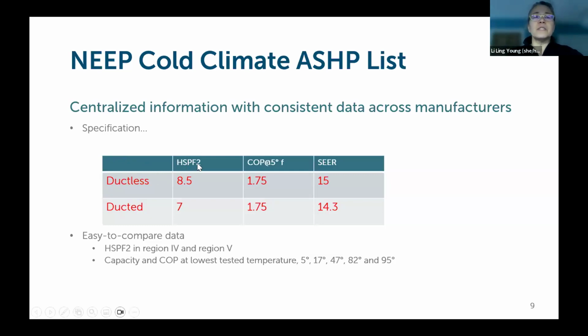So the HSPF is the seasonal efficiency. The COP is a point-in-time efficiency, so it's saying at 5 degrees, these different kinds of heat pumps need to be at least 175% efficient. That's what a COP of 1.75 means. And then SEER is a cooling efficiency.